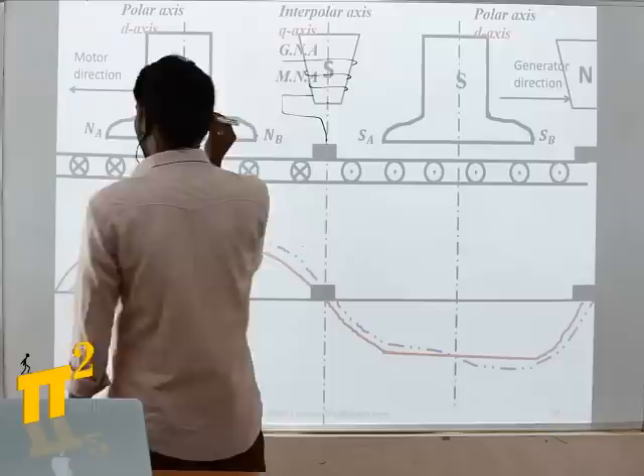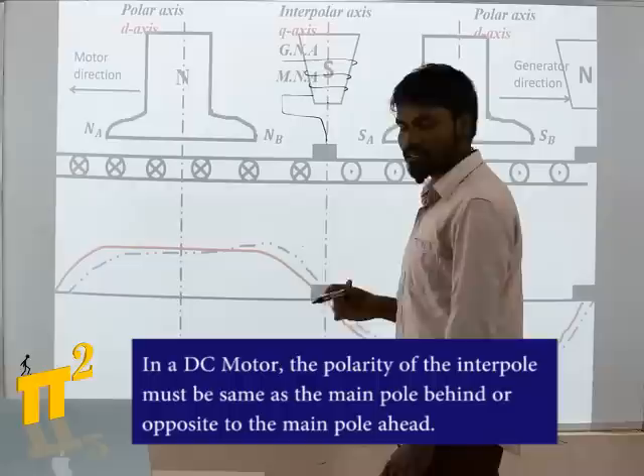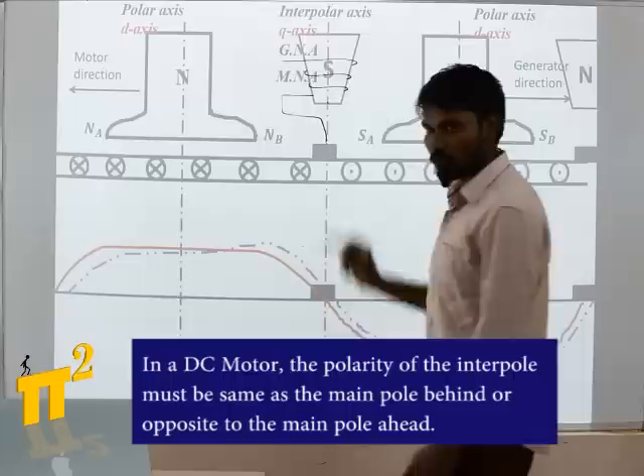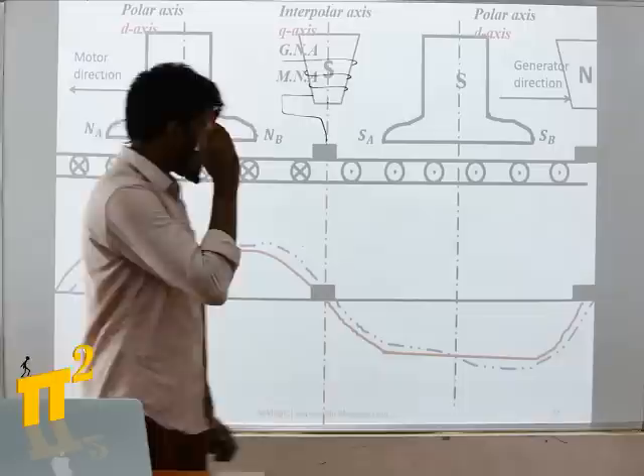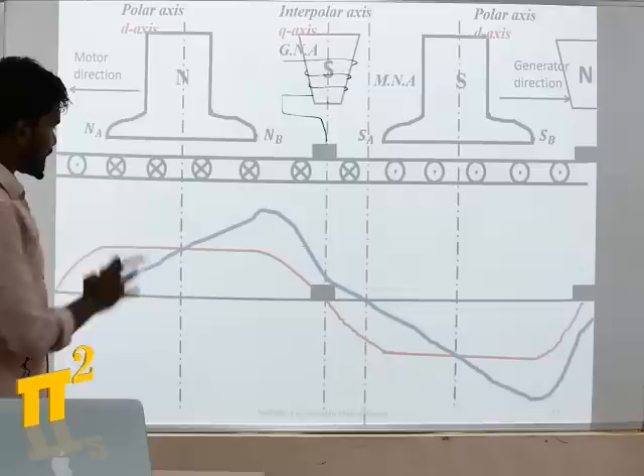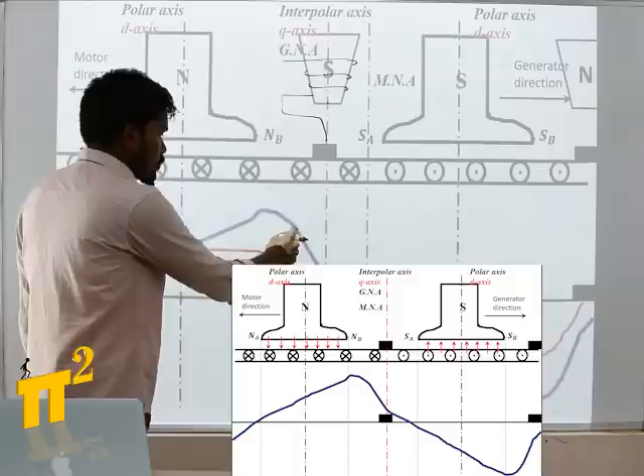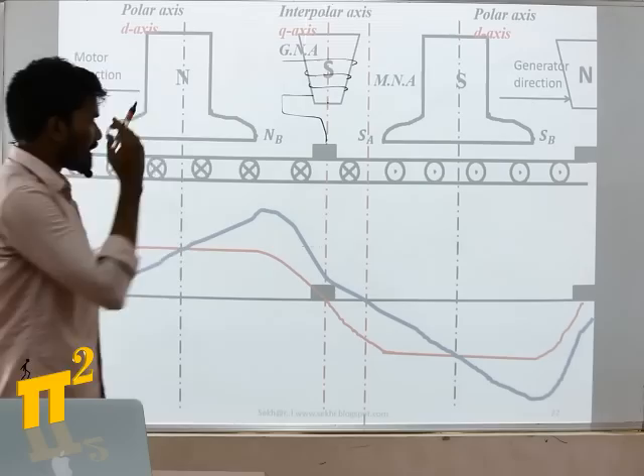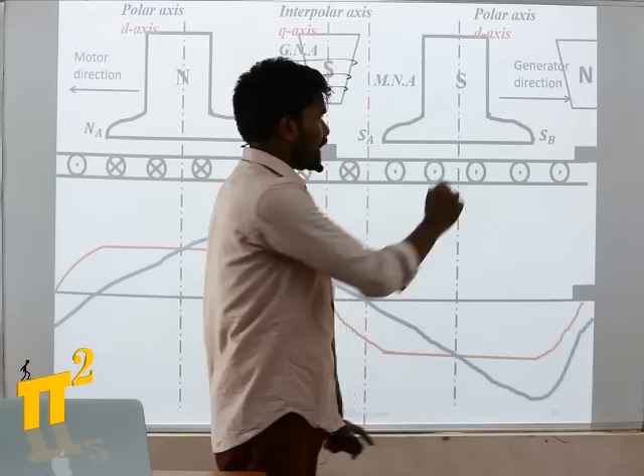For motor reference, the interpole should be opposite to the main pole behind it in the direction of motor rotation. Try to remember the picture: where the resultant flux is more peaky, the interpole suppresses that by having opposite polarity. In the picture, with generator rotation clockwise and motor counterclockwise, fix this visual in your mind so you can determine the correct interpole polarity automatically.